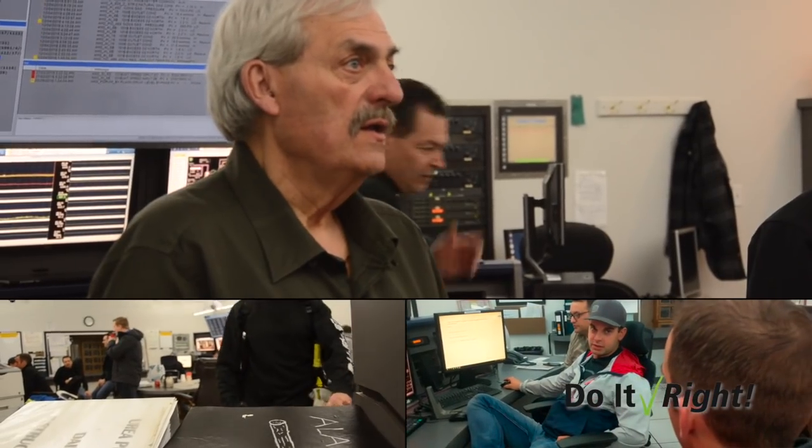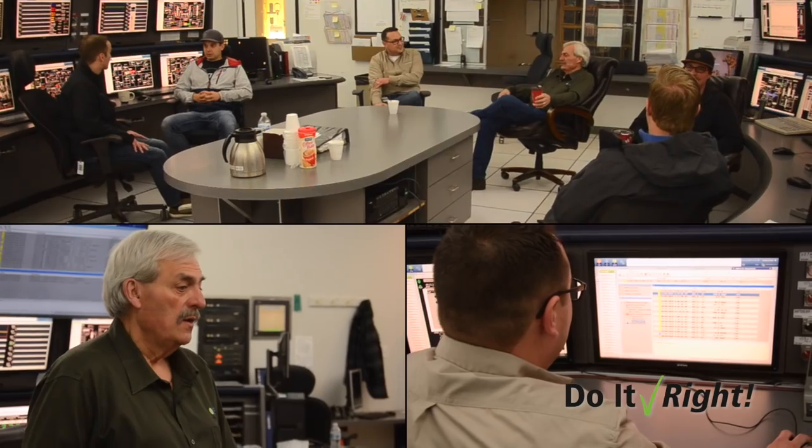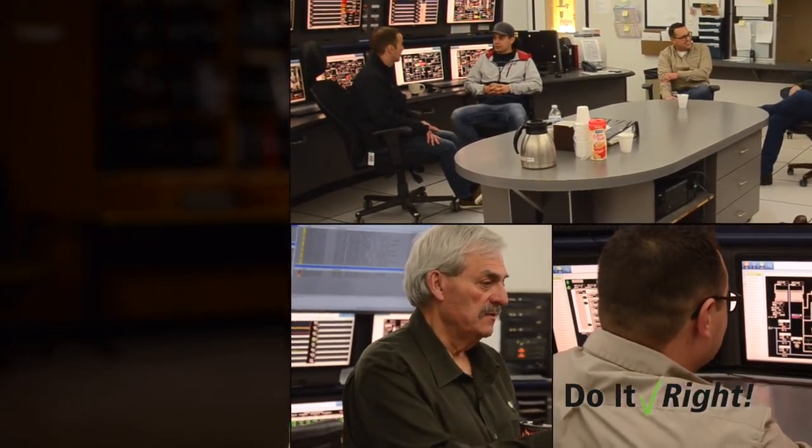It took us over a year to develop our philosophy, and it was a cross-departmental team. We had some maintenance people, some instrumentation people, we had process engineering involved, and a couple of operations people. I remember we would have these discussions where people were saying, this is the most important alarm in the plant, and other people were saying, no, this is actually a low priority because they'd never experienced that. The discussions get pretty heated because everybody has a different opinion. There is a commitment to get this thing kicked off and to get it worked all the way through the process, but the benefit is huge.